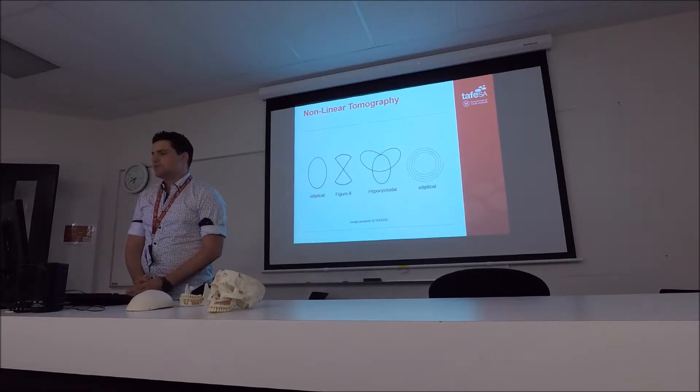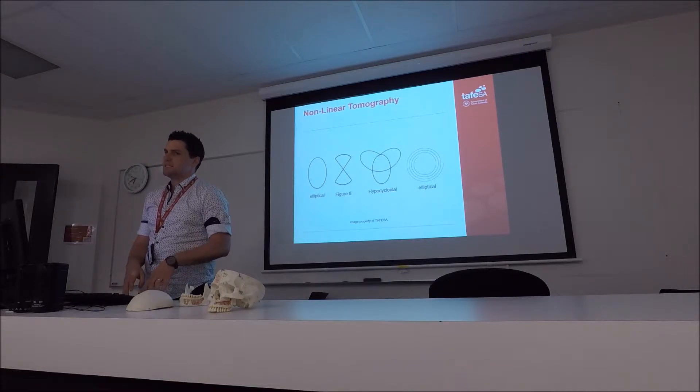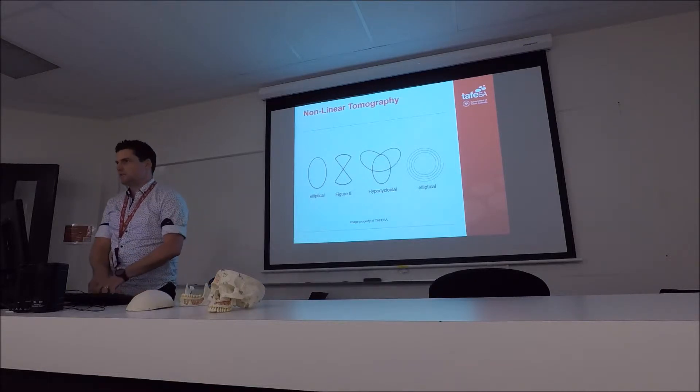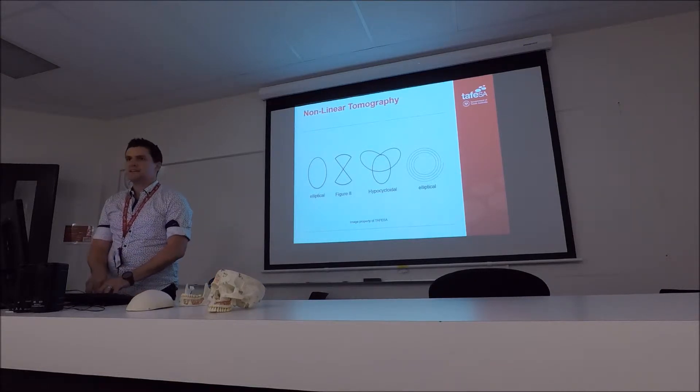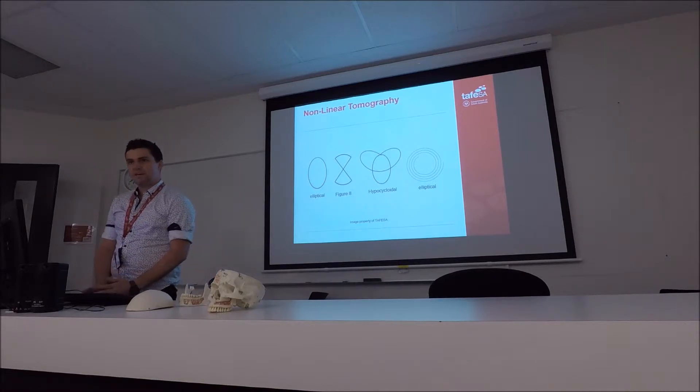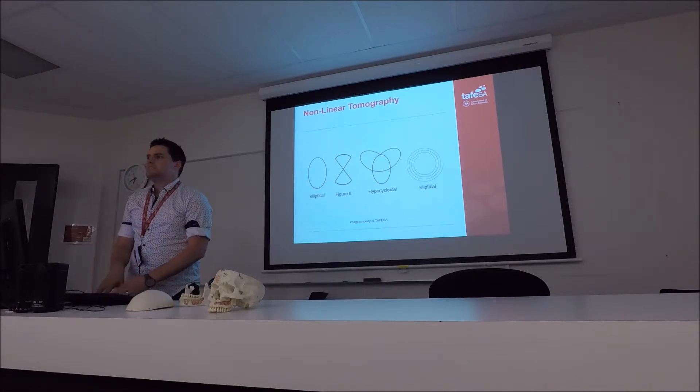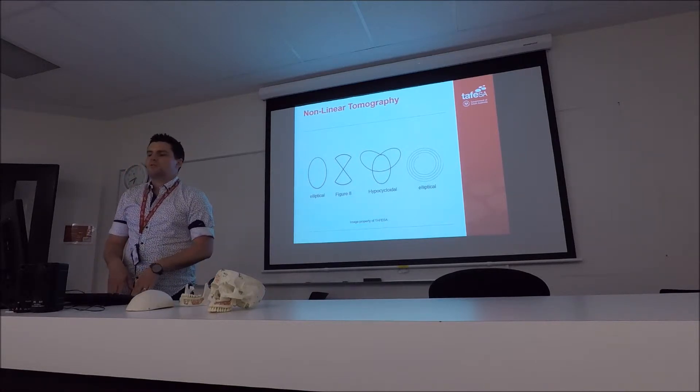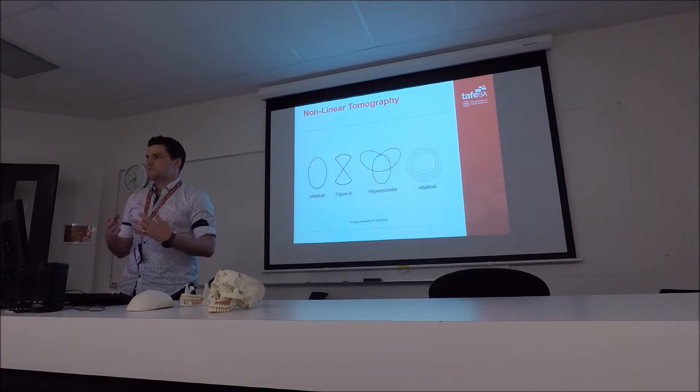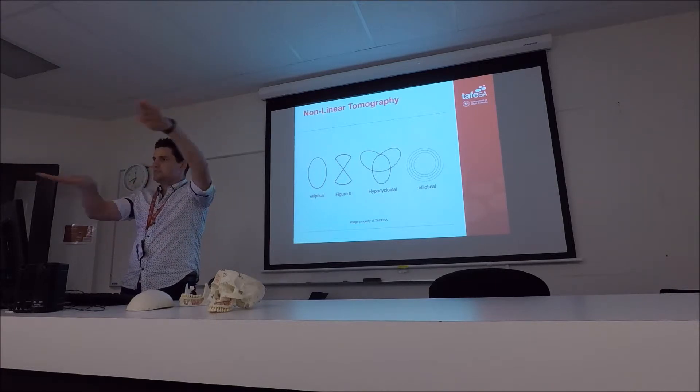So some X-ray units, what you'll notice is, particularly when you're replacing the OPG units at work nowadays, they have a 2D or a 3D function. And the big difference is with a 3D function, it changes the movements. So you've seen this nice linear movement.